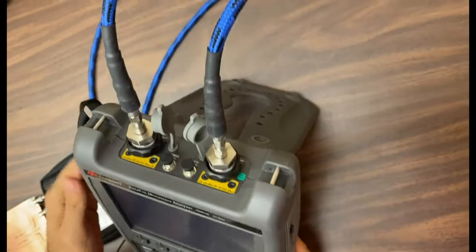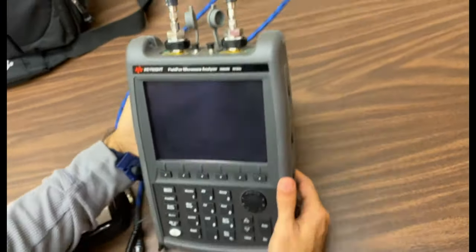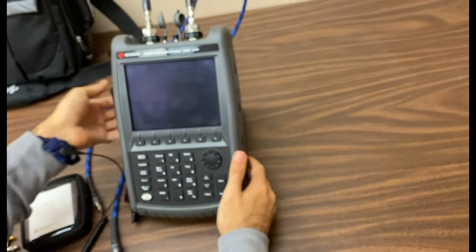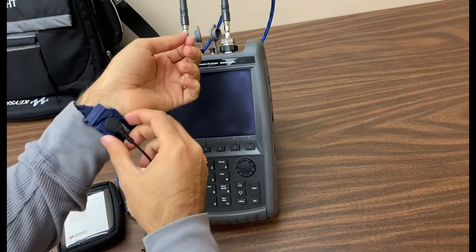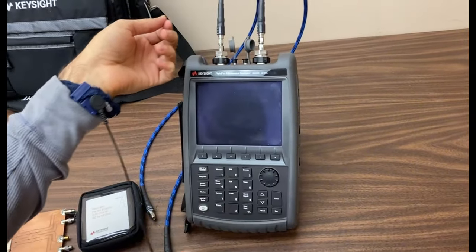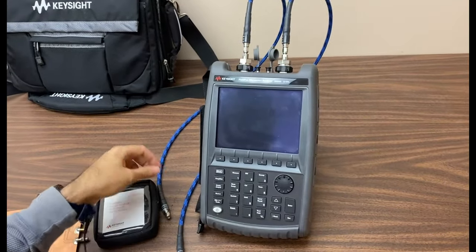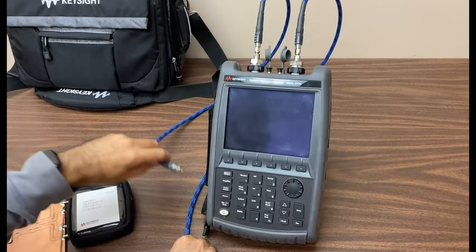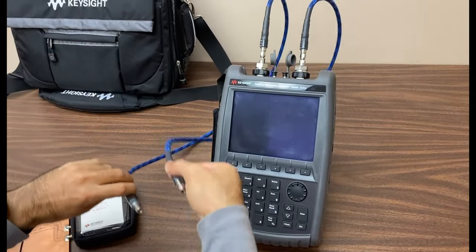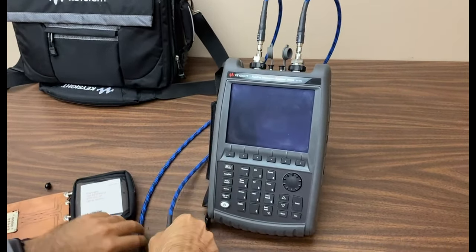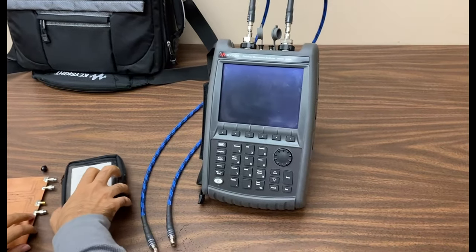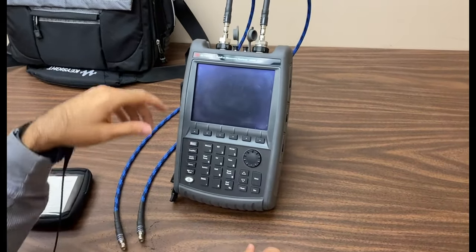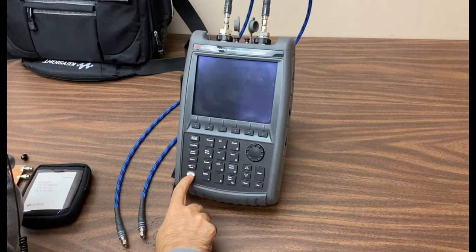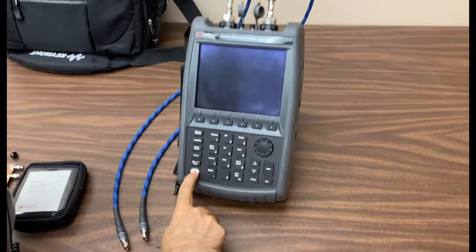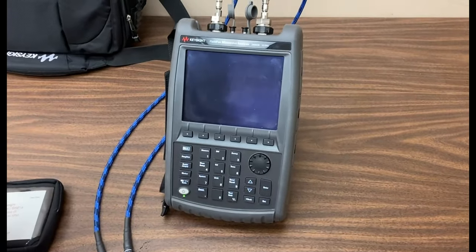Now, as I handle the VNA and its components, you'll notice that I'm wearing an anti-static wrist strap. This is connected to a grounded surface to prevent the buildup of static electricity. Before starting, make sure your connections are secure to avoid introducing errors during calibration. I've already checked the connectors and cables to ensure they're properly tightened. Now, let's power on the VNA. Press the power button to turn it on.